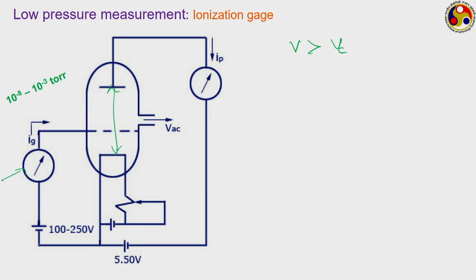That is, the electrons will come out of the molecules, and as the electron passes from the cathode towards the plate and strikes the molecules, it will lead to positive ion formation by dislodging some more electrons. So, the positive ion formation actually is a result of this low pressure gas. Just to clarify, when the gas pressure is so low, that is, at this particular pressure level, we can almost assume that during its passage from the cathode to the plate, there are not too many molecules for the electron to cause more than one collision. So, the number of positive ions produced can then directly be related to the number of molecules present there, and accordingly the pressure inside this cylinder.